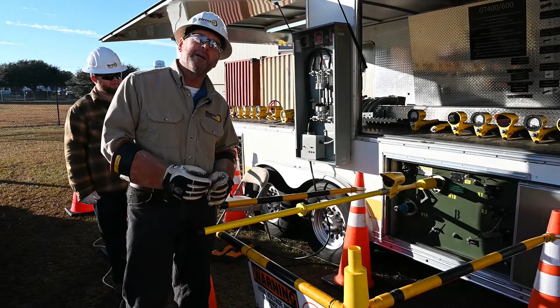We're using a live known voltage source, and the tool's working great. Then we're going to open the switch. We verify that we have an open air gap, and we verify visually the switch is open. Then we're going to retest on that overhead line. We make direct contact, and the tool says we are de-energized.